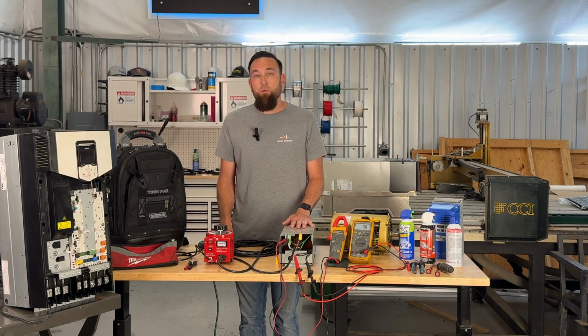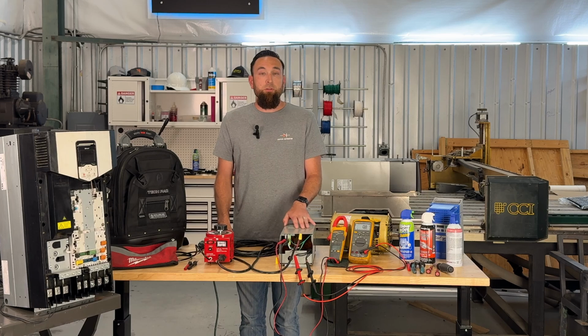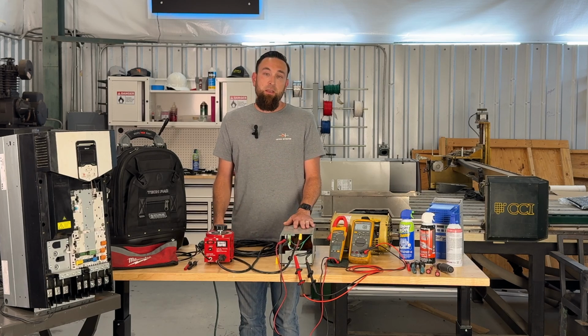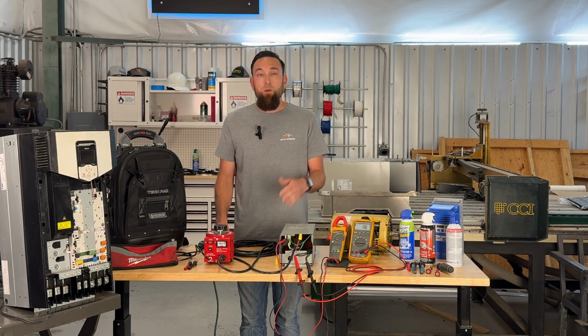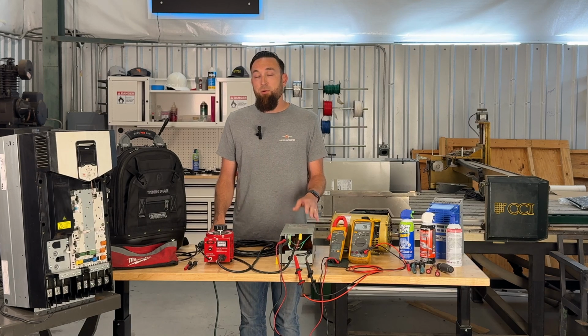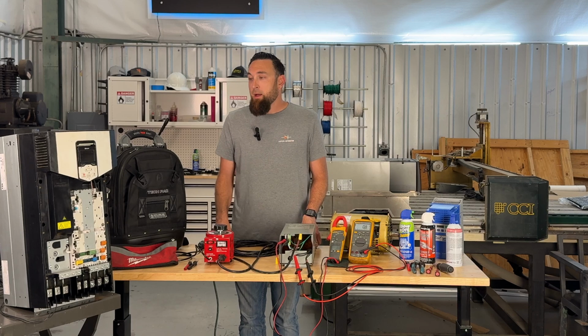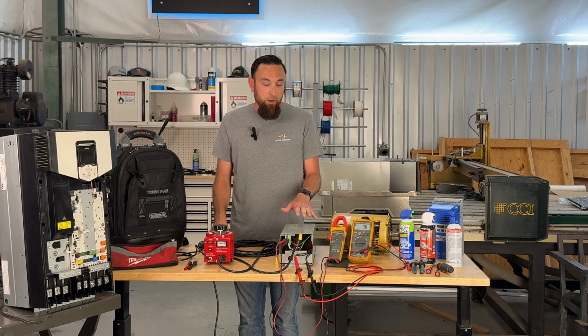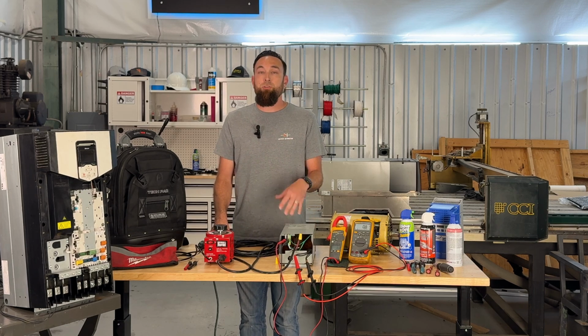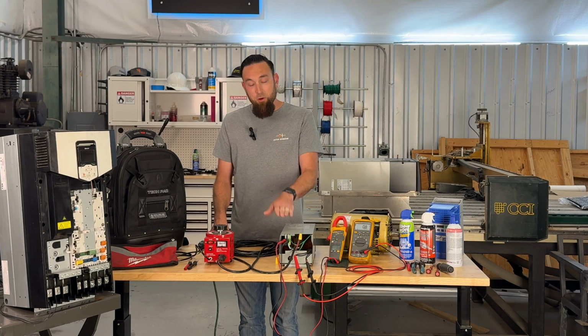With this transformer, we have it wired up backwards so that if we give it voltage on its secondary on the 110 volt side, we will get out of the primary either 460 or 230, depending on how we have it wired. Like I said, this is a 230 volt drive, so we are actually going to wire this with the coils in parallel, and that will give us 230 volts when we give 115 in.